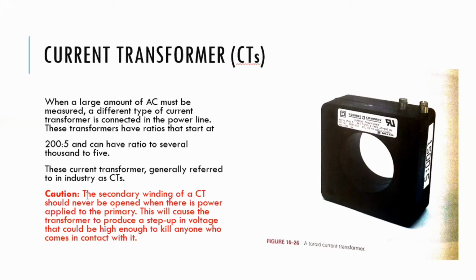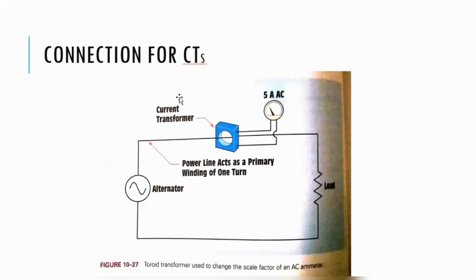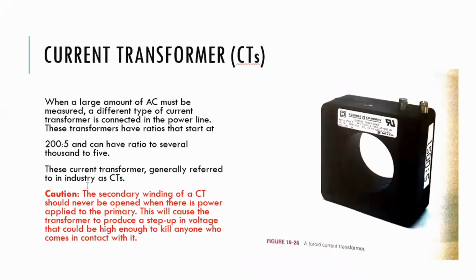Caution: the secondary winding of a CT should never be opened. Right? There is the secondary winding which is wound in the CT. The secondary winding of a CT should never be open when power is applied to the primary. This will cause the transformer to produce a step up in voltage that could be high enough to kill everyone who comes in contact with it.